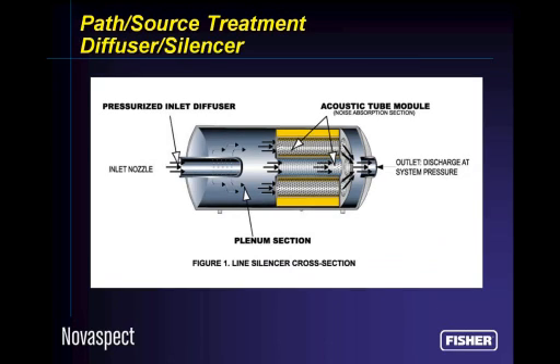We'll use a silencer in combination with a diffuser in order to reduce noise if we can't do it by the valve trim alone. The diffuser is this device. It's nothing more than a piece of pipe with a whole bunch of holes, and we'll use up part of this system pressure drop as drop across the diffuser, which reduces the pressure drop across the valve. And by reducing the pressure drop across each one of those devices, we can frequently end up with a total combined noise level that's less than we could do with a valve alone. If we still need to do some attenuation, we'll do that with some noise absorbing material in the silencer. It'd be a Teflon base packing material or whatever, in order to be corrosion resistant and yet absorb noise, like a muffler, if you will.